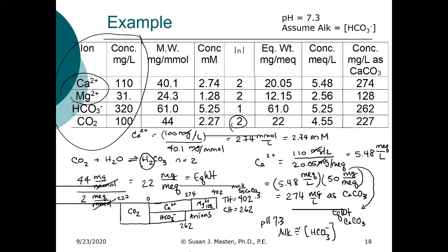Where does the 262 come from? It's that portion of your hardness that's associated with alkalinity. That part that you just highlighted, that relates to the carbonate hardness, right? Correct. Okay, thanks. And if you are not muted, if you could make sure you mute yourself. So I just highlighted, okay, this is our carbonate hardness. So it's that portion of the calcium that's associated with bicarbonate.